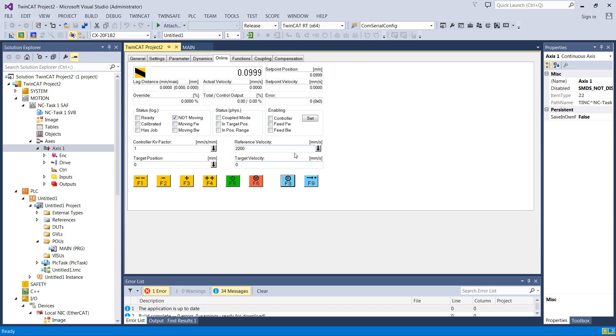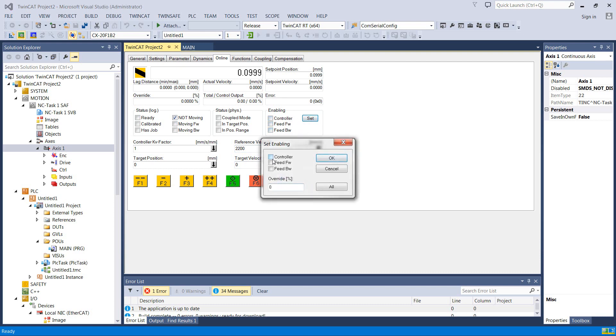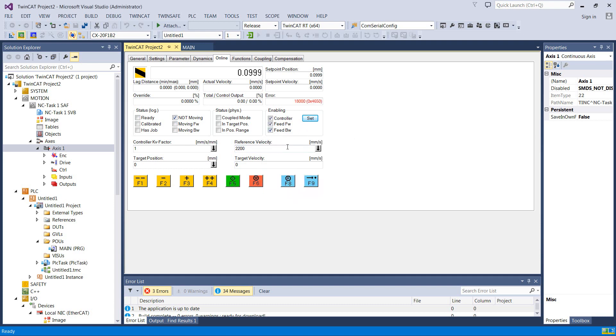So when that comes and goes, you've got to reset this drive and stuff like that. So the other thing you need to do is enabling feed forward, feed backwards, and controller enable. You need to have these set. So these are like limit switches and the actual controller enable. Normally, you would set that from the PLC, but this is a good place to get those set. So here we've got an error. We can reset that.